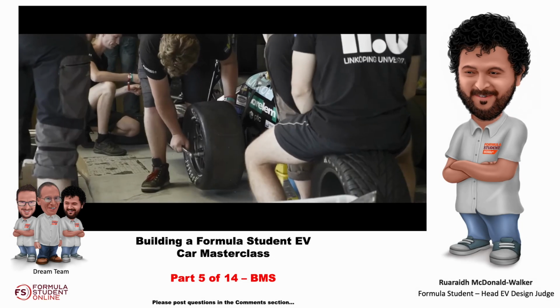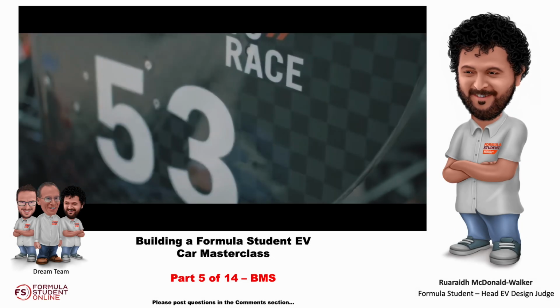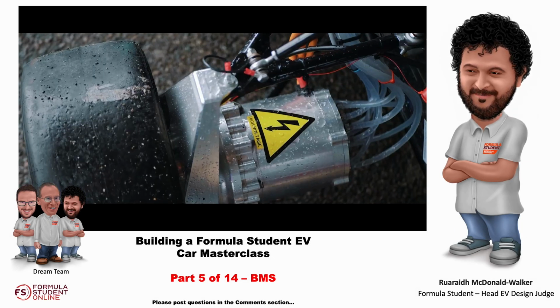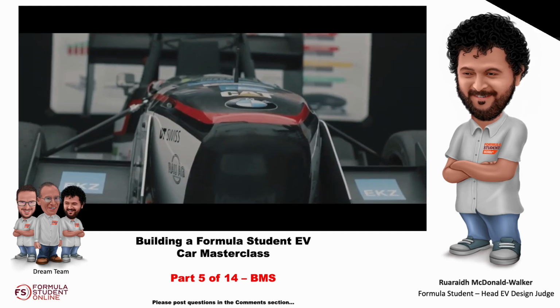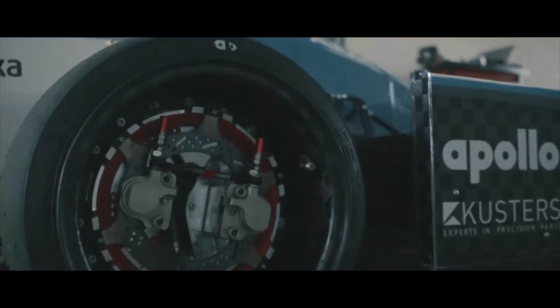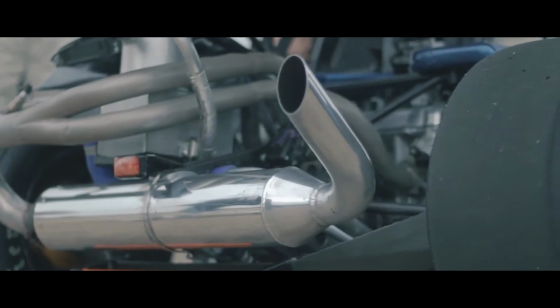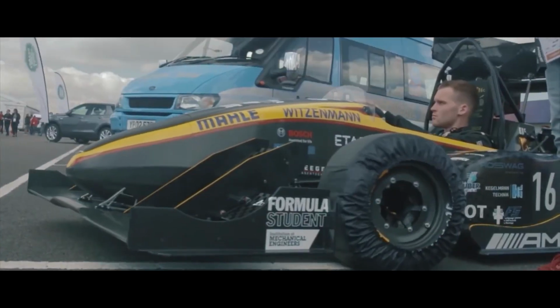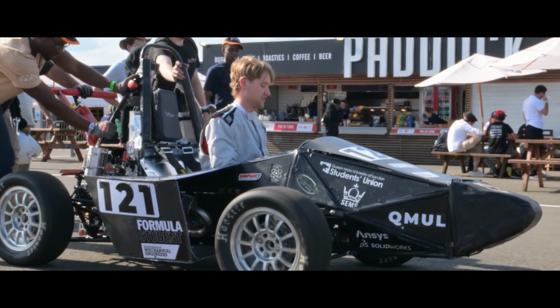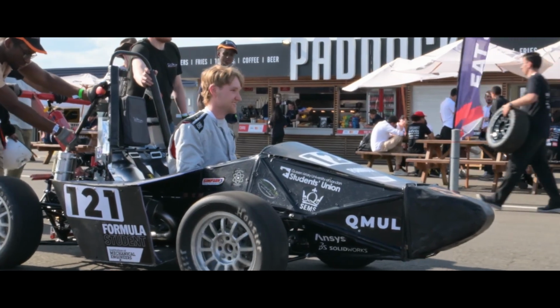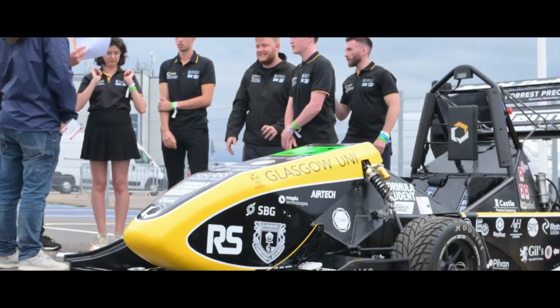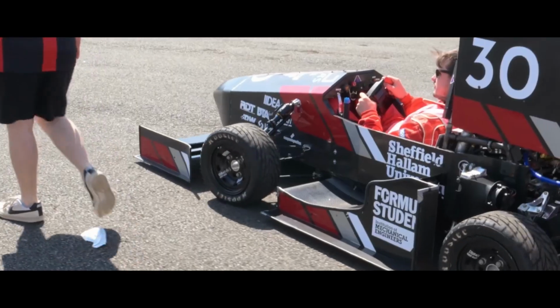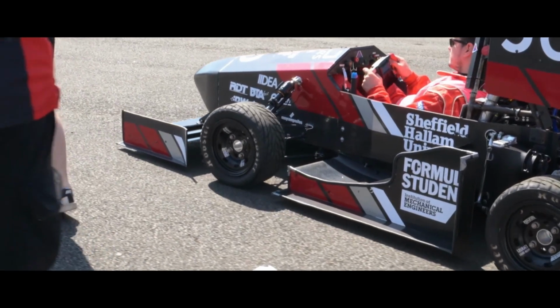So you've got your series, you've got your parallel, you understand what cells are, modules and batteries. What's a BMS then? The really important thing to understand about a lithium battery, a lithium cell more specifically within that battery, is that you have to operate it within very set limits in terms of its voltage, minimum and maximum voltage, its currents, and its temperatures. The battery management system is what helps you do that.